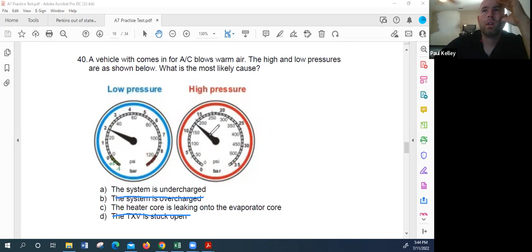Now, in California heat, this may seem a little bit low, but remember, this is a test for the whole country. So I'm leaning towards, I don't think this system's undercharged either. If it was 97 degrees, these numbers would be too low, but 97 degrees is kind of an exception. So let's assume it's 80 something in the summer. These numbers probably are more in line. I don't think it's undercharged.